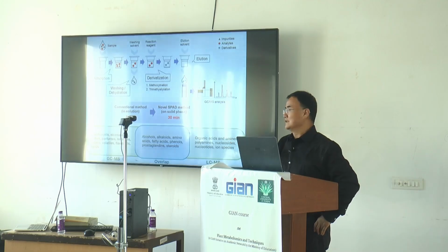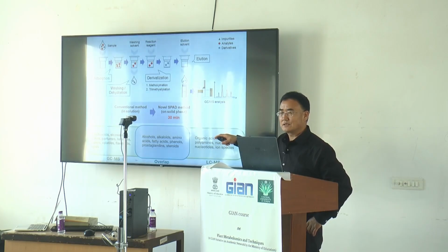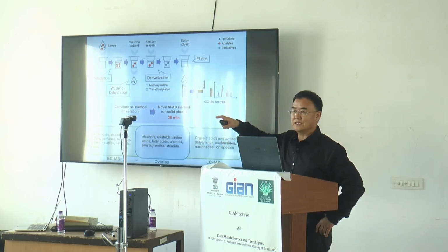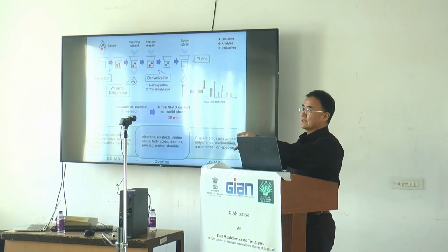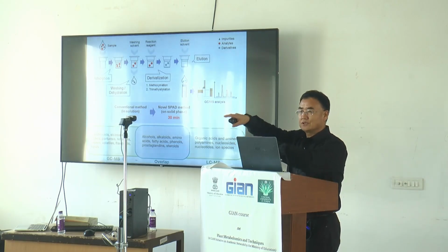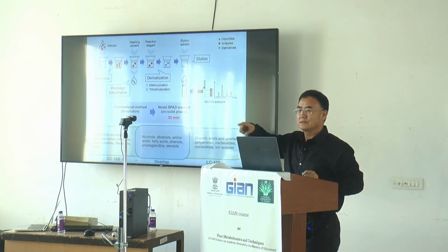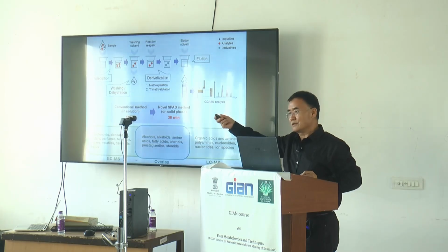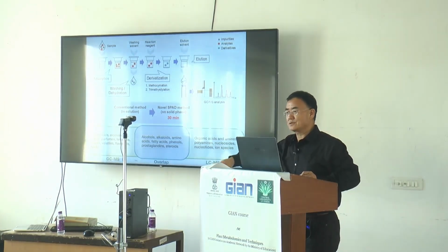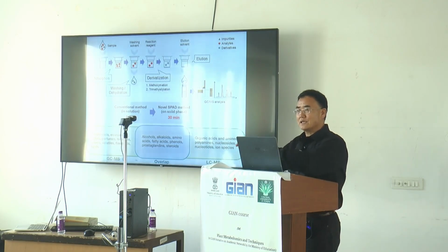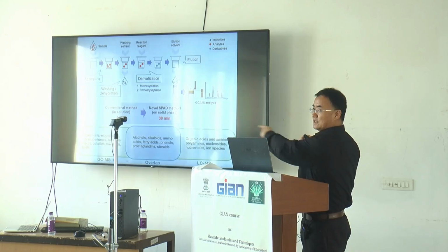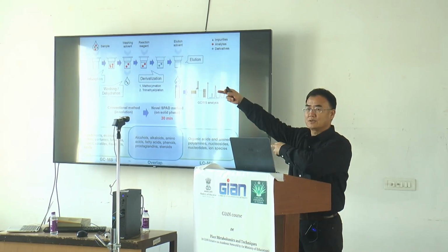For some metabolites, depending only on the mass is probably not enough. For example, for flavonoids, people also use the DAD or PDA detector. I mean, one time you pass through a small chamber, we get UV scanning from 200 to 800 nanometers, so you get the absorption. This gives you one piece of information. Then it goes to the mass spectrometer, and about 10 minutes later it gives you another mass spectra identification result. So you can, according to the mass spectra, total ion and retention time, match back to the UV absorption.